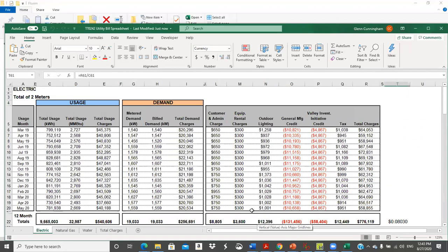Anyway, these guys were running 95. When you looked at it, it was 95, 95.2. There might have been a 94.8 or something like that. But it was right there. And you look at that and you go, you guys are correct, aren't you? And walk in and say, yeah, we got capacitors all over this place. And it's obvious they had already worked the problem. They'd already solved it.